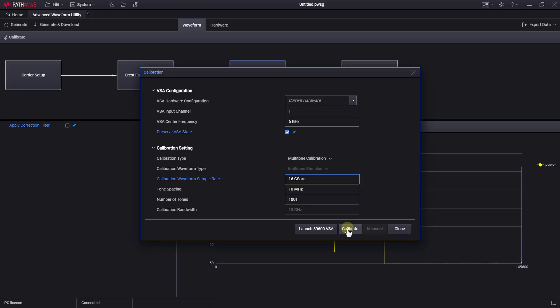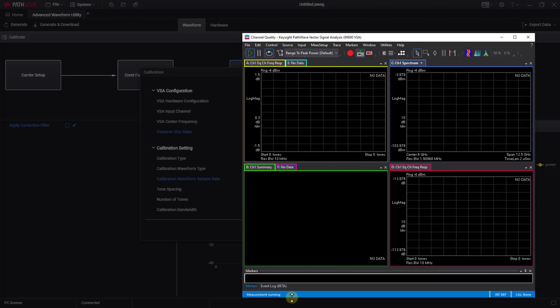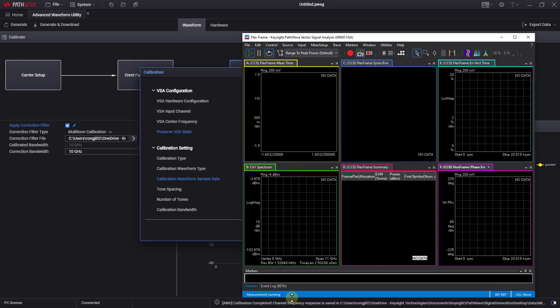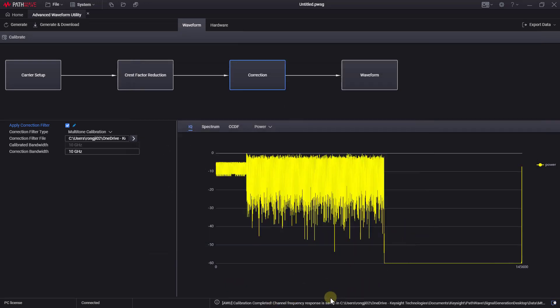So, we'll leave them as is. Now, we can click the calibrate button, and the calibration process will start automatically with the VSA. After a few seconds, we can see the message that the calibration has been completed, and the correction file has been applied and saved on our local drive.